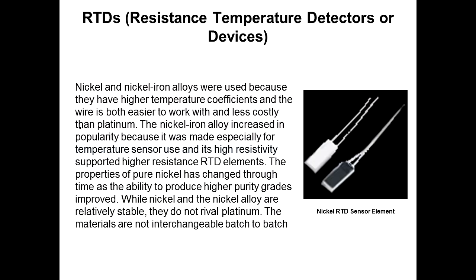Nickel iron alloys were used because they have higher temperature coefficients, and the wire is both easier to work with and less costly than platinum. The nickel iron alloy increased in popularity because it was made specially for temperature sensor use, and its high resistivity has supported higher resistance RTD elements. The properties of pure nickel have changed through time as the ability to produce higher purity grades improved.